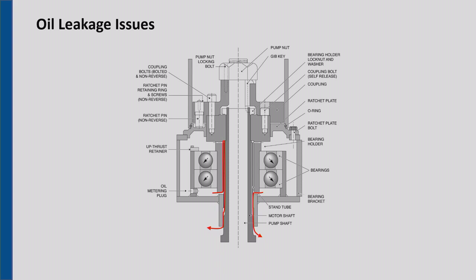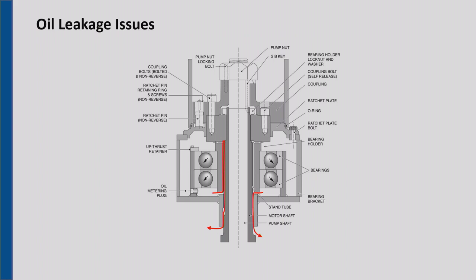Just to explain what's going on, this is a bearing housing on the top of the motor. Okay? There's a pair of angular contact bearings in there, and this is filled with oil to some level. Usually the oil level is right about the middle of the lowest ball. Okay, lowest roller level. So the oil level is about through there.